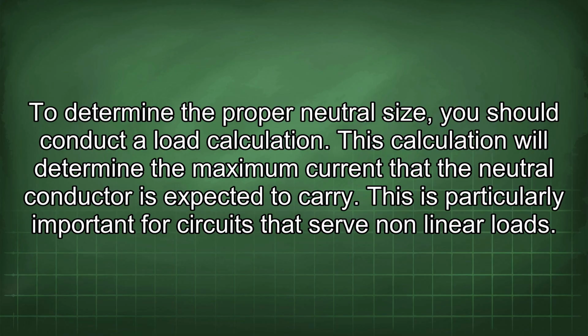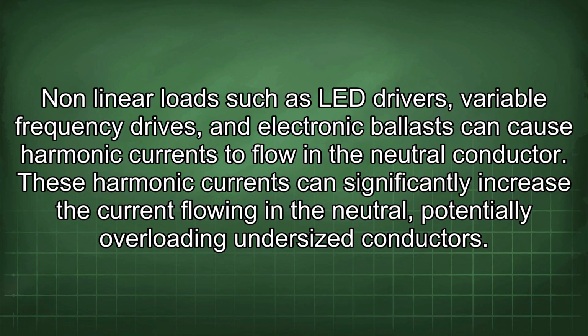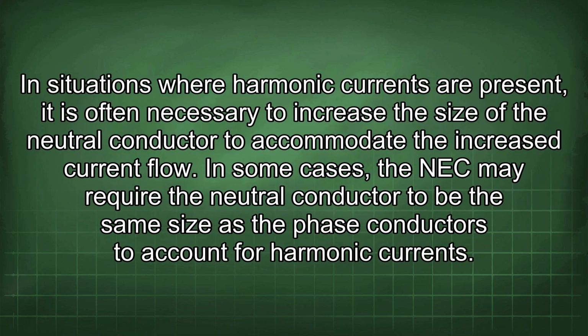This is particularly important for circuits that serve nonlinear loads. Nonlinear loads such as LED drivers, variable frequency drives, and electronic ballasts can cause harmonic currents to flow in the neutral conductor. These harmonic currents can significantly increase the current flowing in the neutral, potentially overloading undersized conductors. In situations where harmonic currents are present, it is often necessary to increase the size of the neutral conductor to accommodate the increased current flow.